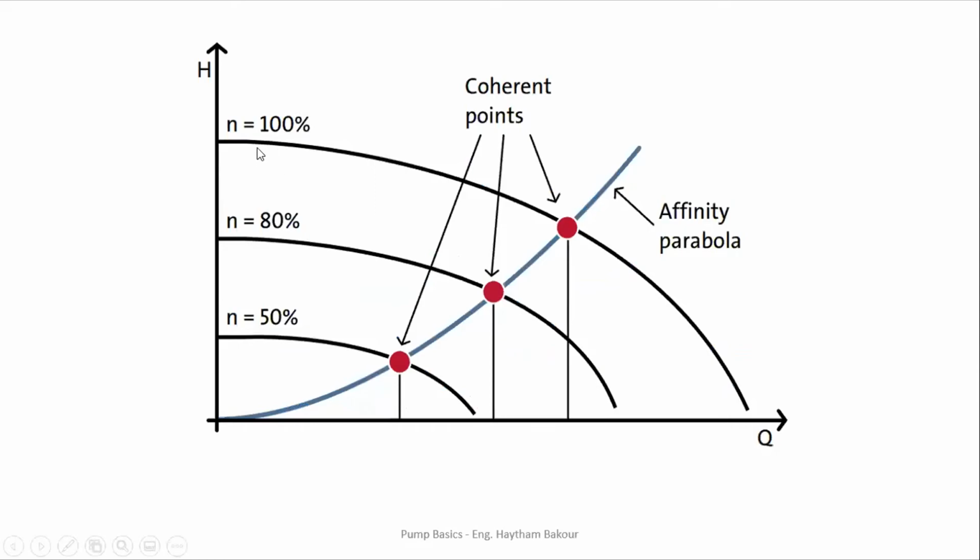When we start the pump at the speed of 100%, we can have the flow rate at its maximum. While when we start it at 80% of rotational speed, the flow rate would drop, and the power would drop dramatically, but in good performance.